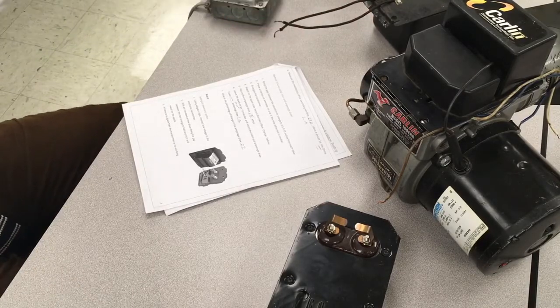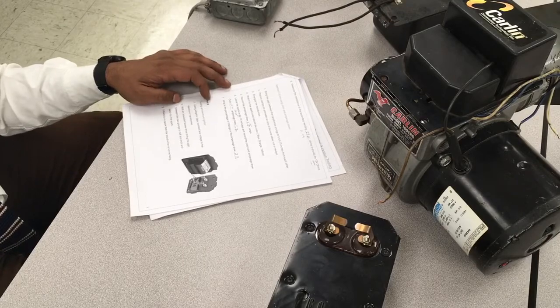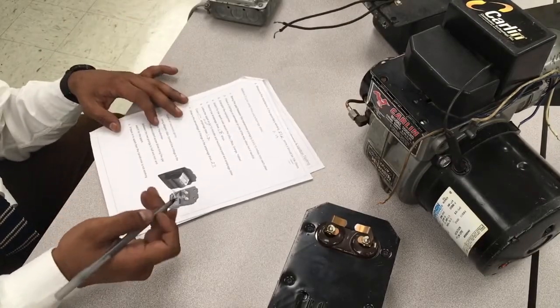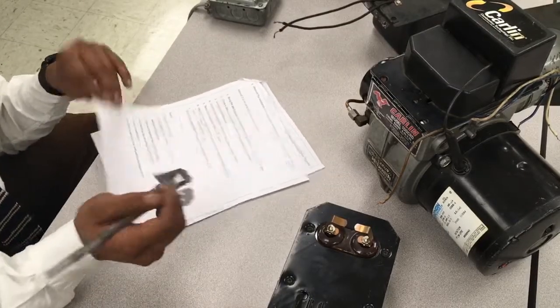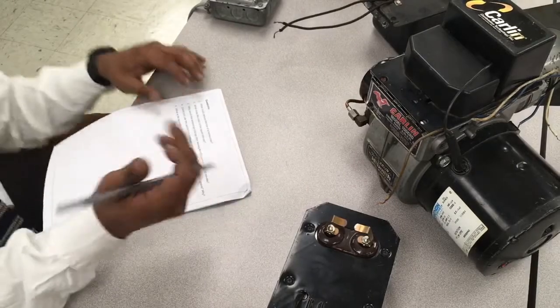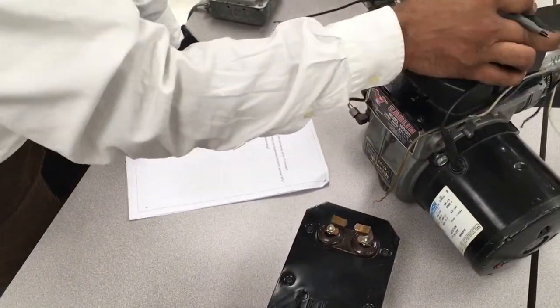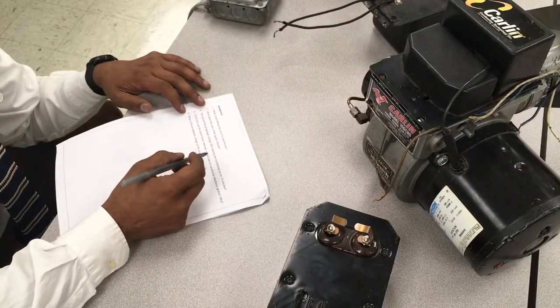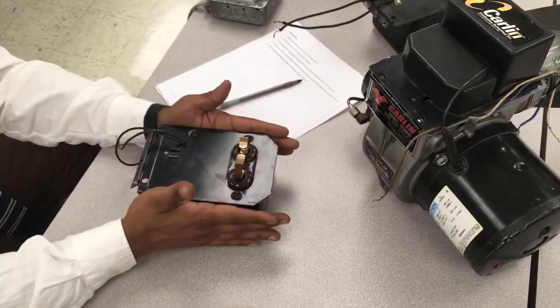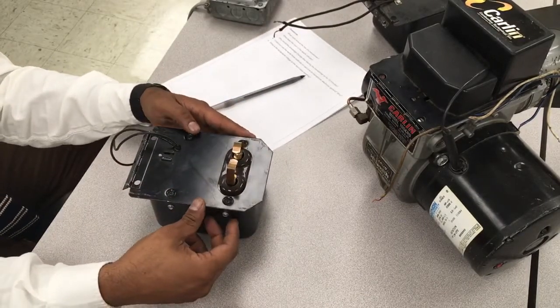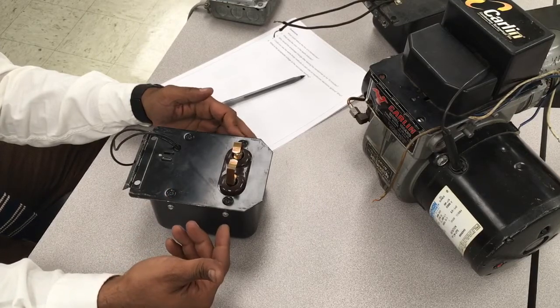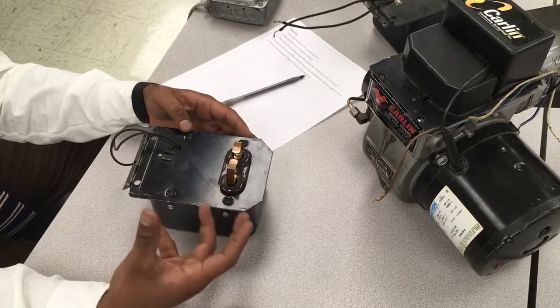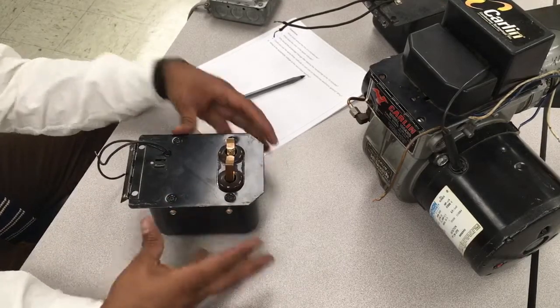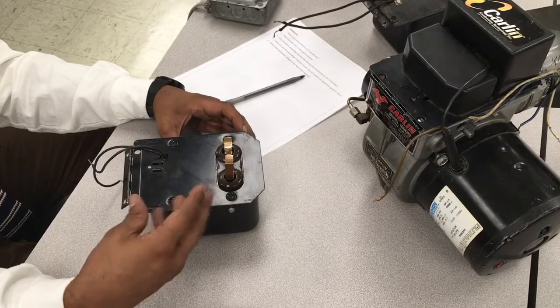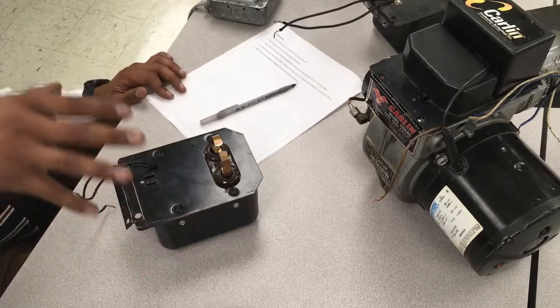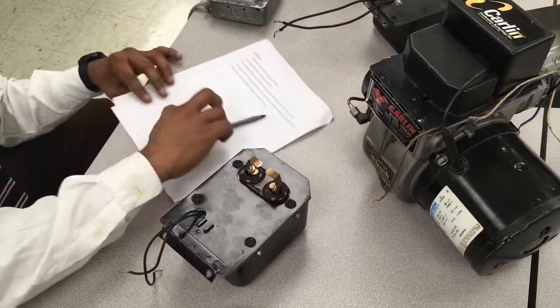And the smaller electronic igniter consumes less energy. But now with having interrupted ignition, it does not consume energy anyway. So this is part 2. We did check the spark, and either it's there or it's not. And make sure again those things are touching the leads inside. Okay, for the questions, what could reduce the life of a transformer? As we said before, the transformer is basically an iron core with a winding inside of copper wire, and this copper wire is insulated with tar. If the tar deteriorates, it will change the magnetism. So make sure you insulate that correctly. It's insulated with tar, so heat can melt the tar and change the magnetism, or if it gets water in it. So water or excessive temperature.